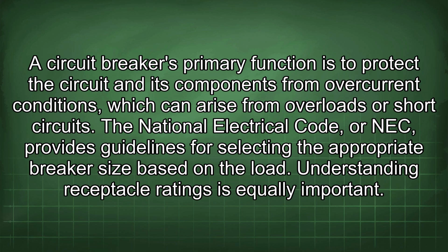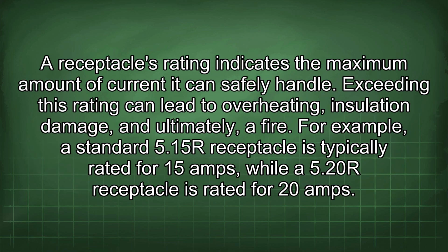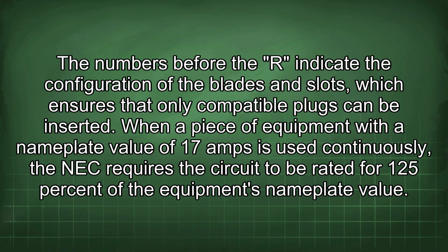Understanding receptacle ratings is equally important. A receptacle's rating indicates the maximum amount of current it can safely handle. Exceeding this rating can lead to overheating, insulation damage, and ultimately a fire. For example, a standard 5.15R receptacle is typically rated for 15 amps, while a 5.20R receptacle is rated for 20 amps.